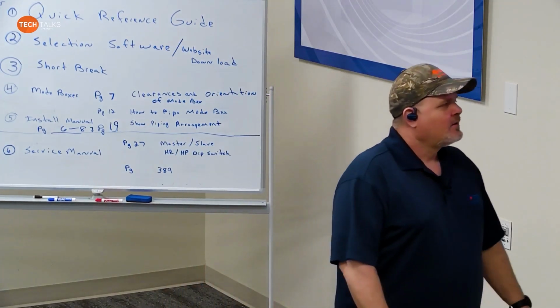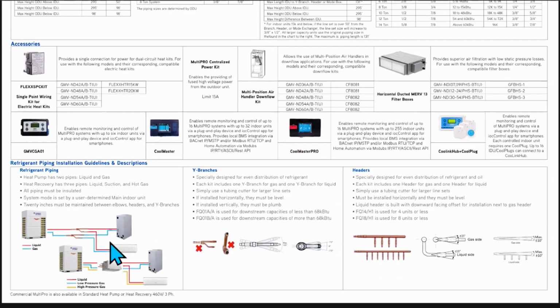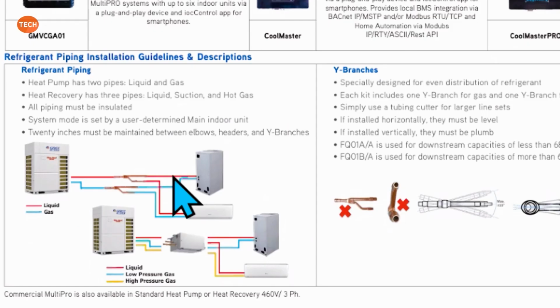Correct. Bring the diagram back up, Robert. Go from a Y branch to an indoor unit, that piping right there. In your smaller BTU sizes, be really careful. When Robert shows you the selection software, you don't know your exact dimensions yet, so you've got to have an idea how long those pipe lengths will be. You build your preliminary selection, then come back with your as-builts and go back in to change the actual piping sizes so you get the correct charge amount.